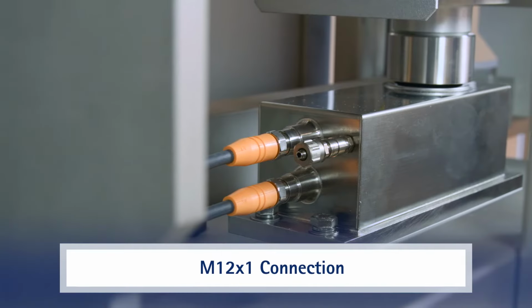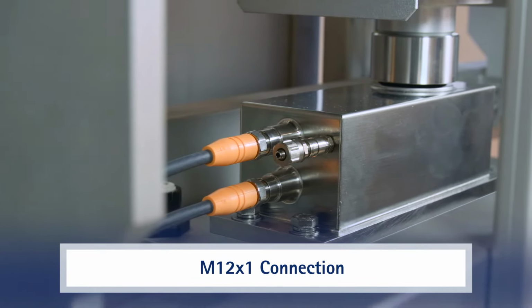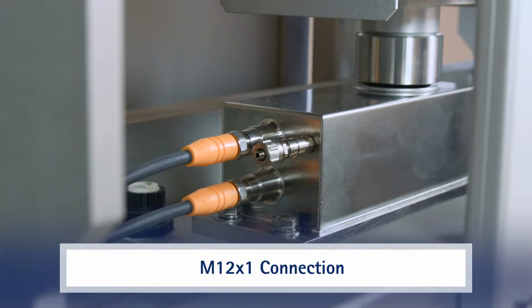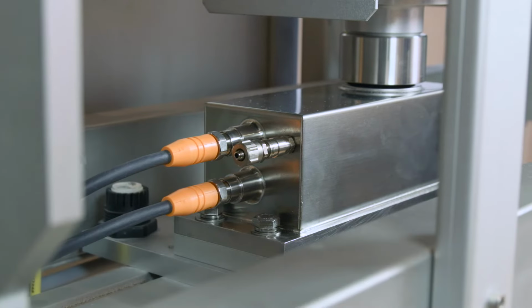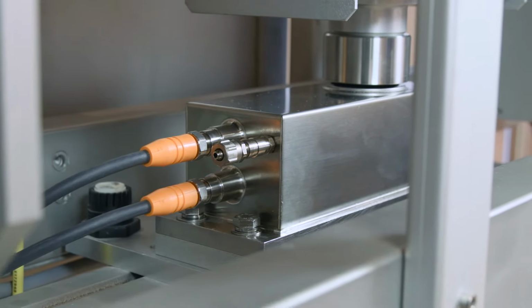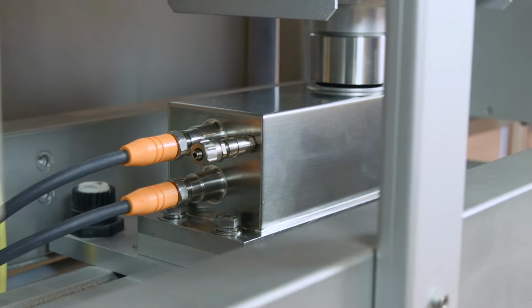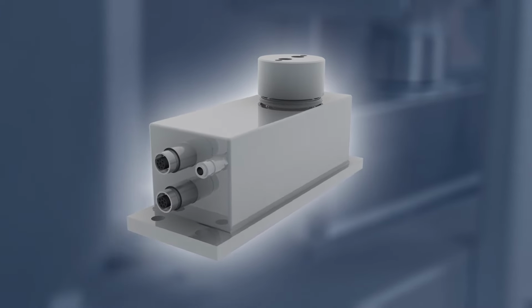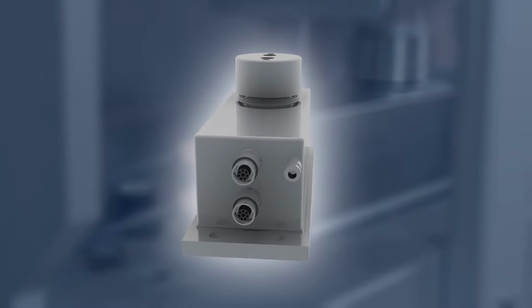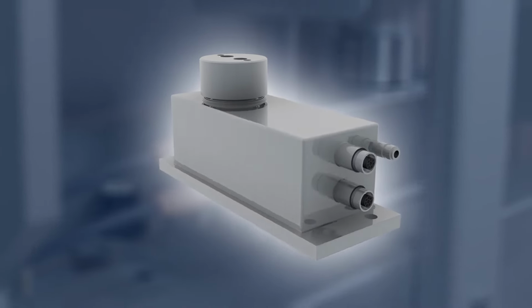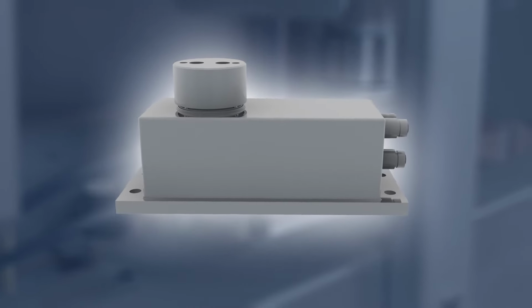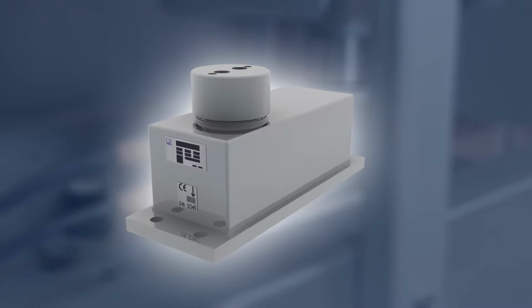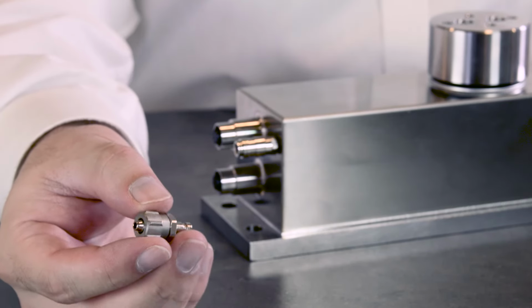The 8-pin M12x1 male connectors and a compressed air connection are located at the rear of the Fit7A. In its original state, the Fit7A is airtight. Changes in ambient pressure will have an impact on the measurement signal. Fit7A comes equipped with a self-sealing compressed air connection and a coupling plug to help eliminate external impact.